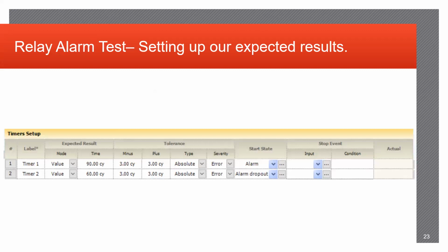I'm just going to highlight this one last little section here, and it's timer values that may be associated with the testing as well. The timers are extremely useful for the state simulation tests because they can indicate when an element needs to be picked up, especially if there's a delay in the logic, because you don't want the relay to initiate a trip based on an instantaneous reading, especially if there's supposed to be a delay in it. Especially common practice for reclose initiates. If a breaker opens from a fault, there's a delay for nominal voltages and currents to return to the relay before initiating another close back into the equipment. The timer section for this setup is pretty handy when utilizing all those state sims.